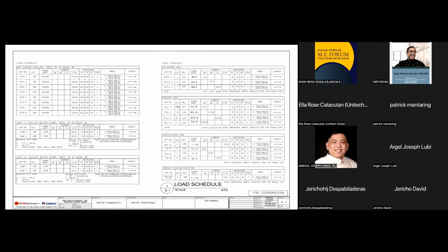Ampere frame, by the way, is basically, in layman's term, the maximum allowable current protection sa casing ninyo, kasi most of the casings we have is based on NEMA classification, the National Electrical Manufacturers Association rating. Sa Unitech, ginagamit natin is NEMA 1, NEMA 3R, and NEMA 12, depending on the situation.